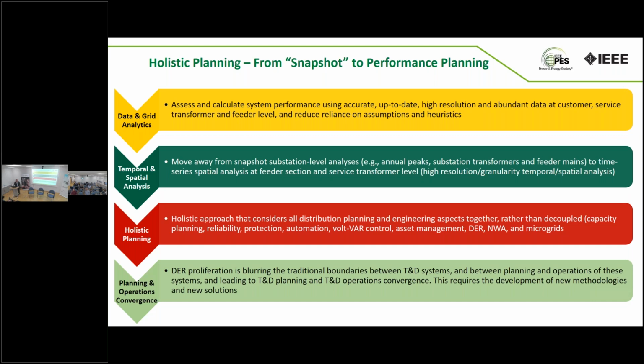The transition now is to high resolution from the point of view of temporal resolution. Instead of focusing on one hour of the day, let's look at every single hour, 8,760 hours of the year. Why? Because now we have DER, and overloads may happen not just once but throughout the year. The other aspect is spatial granularity - looking at every service transformer, every line. It's a more detailed approach to planning.